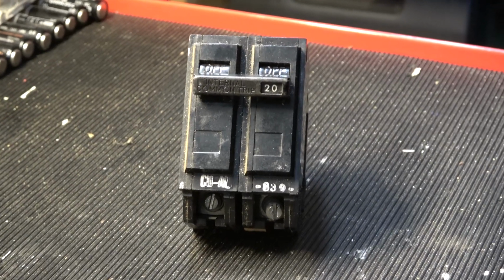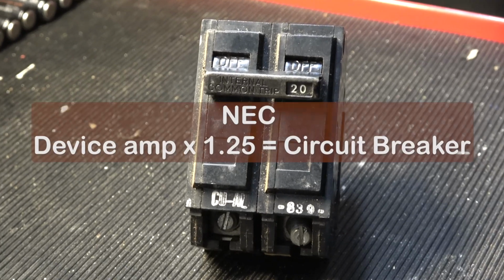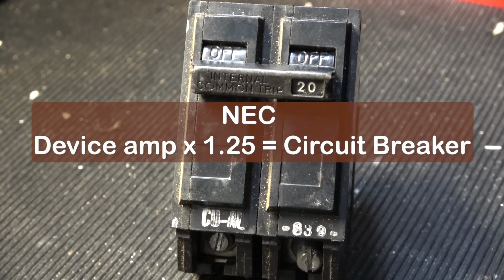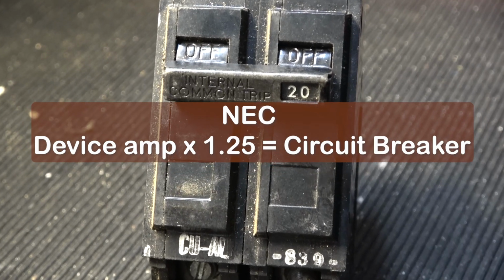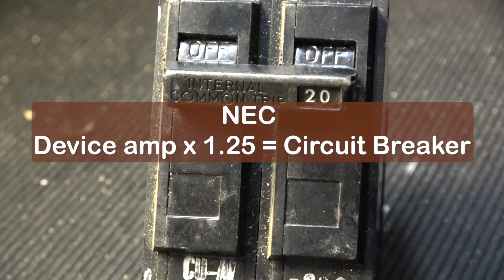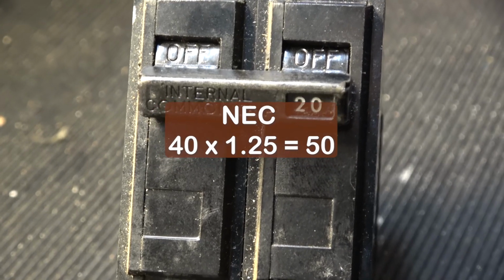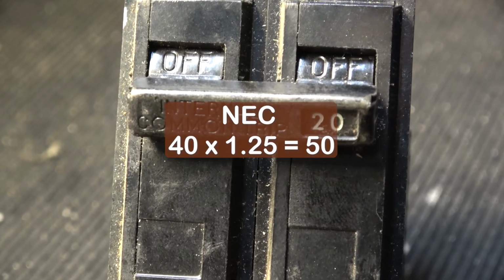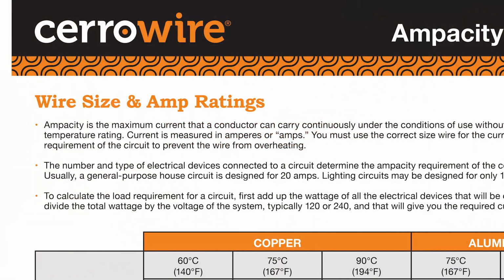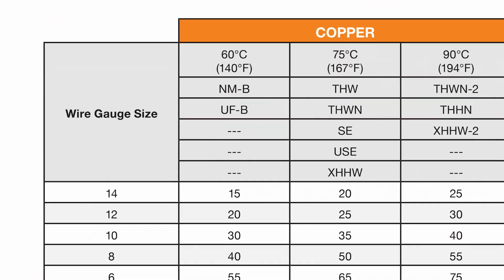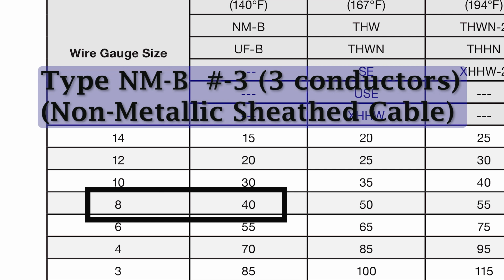Now I needed to determine the circuit breaker that I would need, and per NEC code, device amps times 1.25 will tell you the type of circuit breaker that you need. In my case, 40 amps times 1.25 equals 50 amps. Now this number allowed me to determine the conductor size that I needed for the cable. NM-B 8/3 is rated for 40 amps, which is too low, while NM-B 6/3 is good for up to 55 amps. Thus, 6/3 would be our cable of choice.